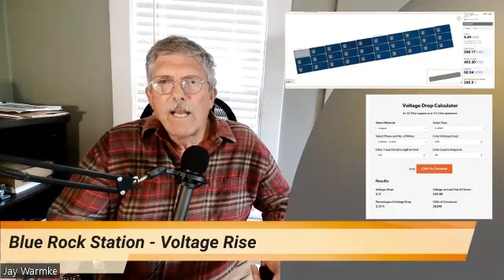But what does this mean as far as what problems can you get into? Well, typically, if you are seeing voltage drop on your system, it's a money thing primarily. We are just saying you're losing 5% of the output of your array. Well, that's not great. I mean, let's say if you just spent $20,000, 5% of that is going to be, what, $1,000. So you just lost $1,000 due to voltage drop as far as the value of the output of your array. But other things that you've seen when you see voltage drop is dimming of lights, motors running not at their peak efficiency. So it can cause wear and tear on some of the load structure within your system dealing with that voltage drop.